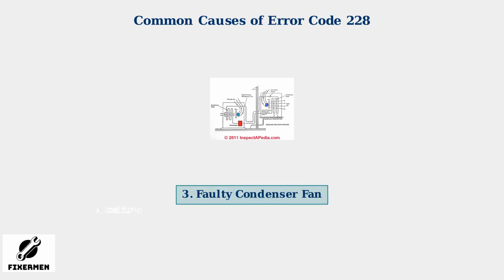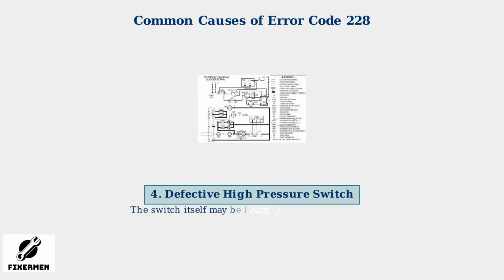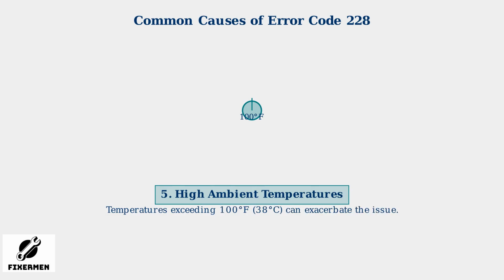Third, a faulty condenser fan. If the condenser fan isn't working properly, it can't pull air across the coils effectively. This leads to poor heat dissipation and rising refrigerant pressure, which triggers the high-pressure switch. Fourth, a defective high-pressure switch. Sometimes the switch itself fails, either staying open when it should close or giving inaccurate pressure readings, causing the system to register error code 228 incorrectly. Finally, high ambient temperatures. When outdoor temperatures rise above 100 degrees Fahrenheit or 38 degrees Celsius, the refrigerant pressure naturally increases. This can push the system beyond safe limits, triggering the error code.